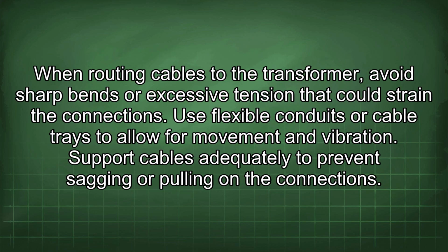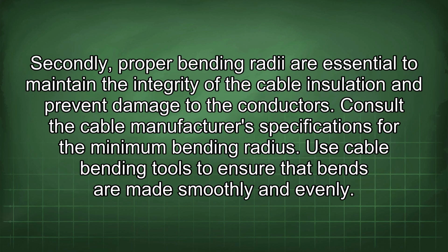When routing cables to the transformer, avoid sharp bends or excessive tension that could strain the connections. Use flexible conduits or cable trays to allow for movement and vibration. Support cables adequately to prevent sagging or pulling on the connections. Secondly, proper bending radii are essential to maintain the integrity of the cable insulation and prevent damage to the conductors.